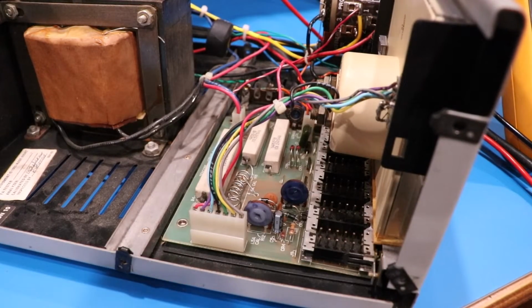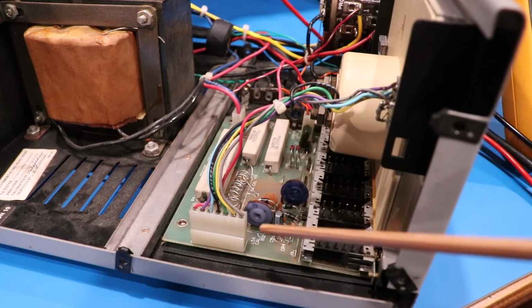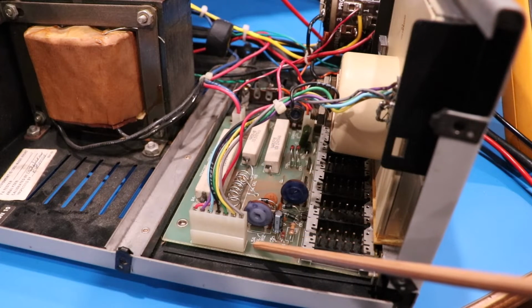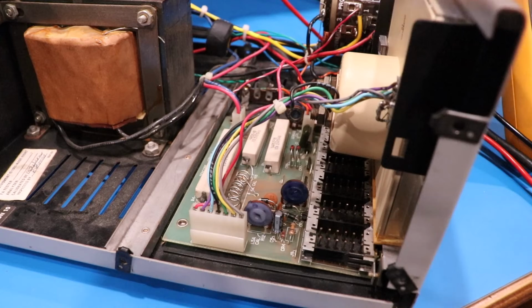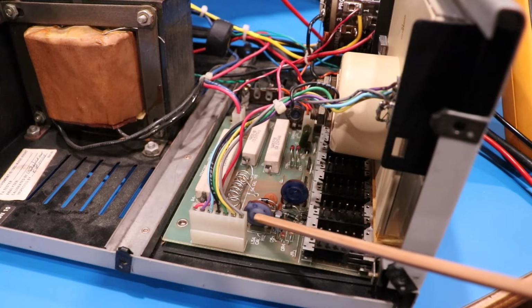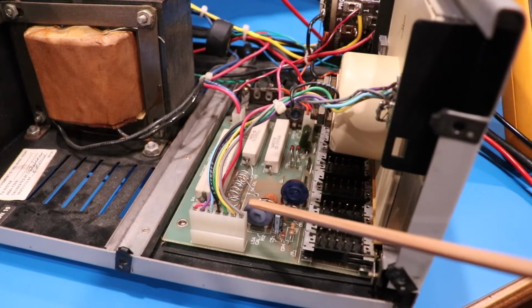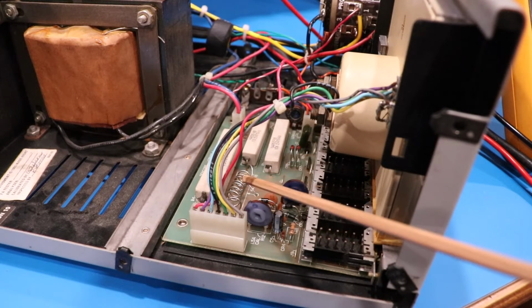Okay, there's really 4 calibration settings inside of this unit. The first one here, if you'll read it on the board, says 1.5 amp calibration. So there's a current setting on this, and there's 2 ranges. There's a 4 amp range and a 1.5. So this would be for aligning the current. I haven't even made it that far. I got to get the voltage right.